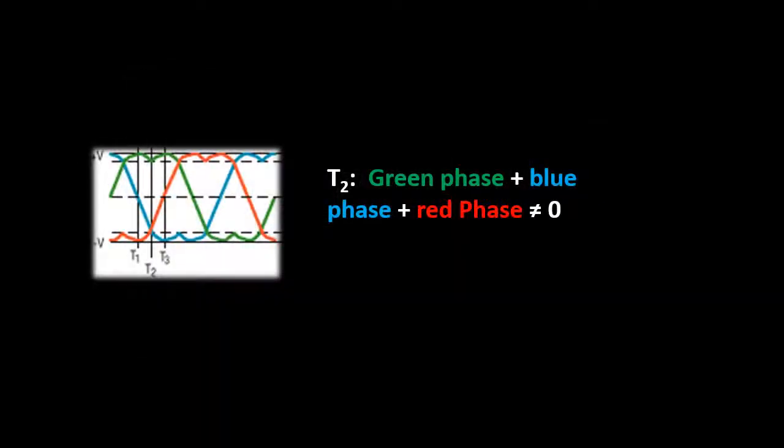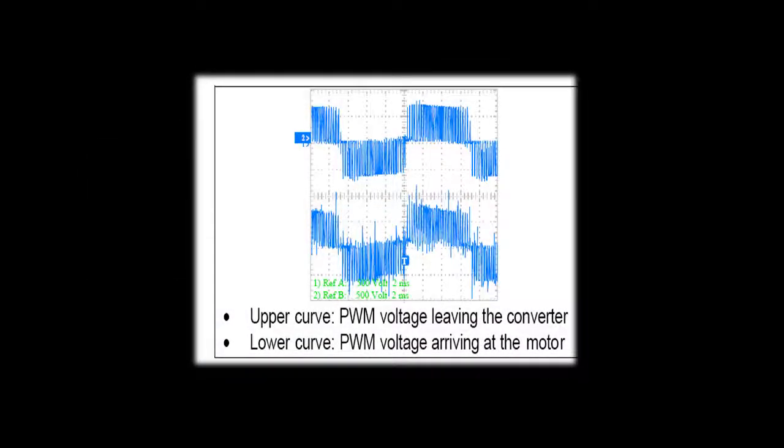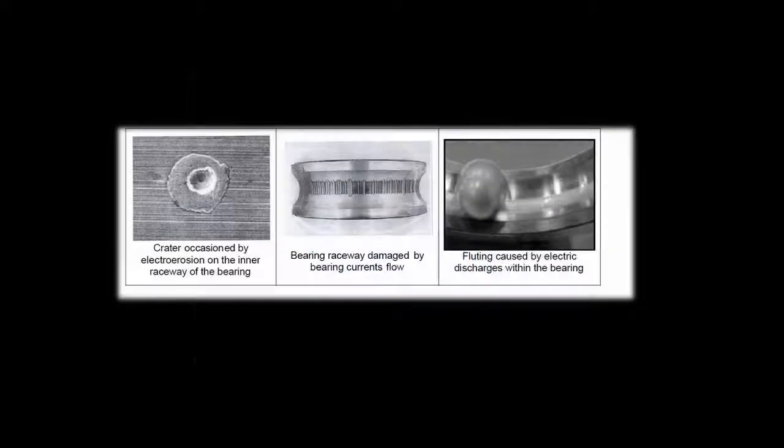Non-sinusoidal switching patterns, such as space vector modulation, as well as transient spikes, can also contribute to this induced voltage on the rotor. This voltage is referred to as the common mode voltage, and leaks to earth through the rotor bearings, causing damage in the process.